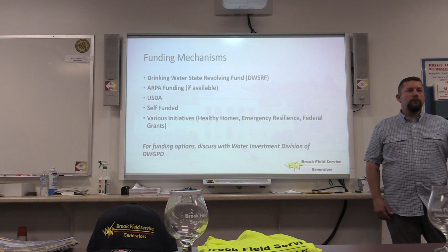Yeah, they have very good data. The one thing you have to remember with the data you're getting from them is that they're measuring in 15-minute increments. When a pump comes on, it's a lot faster than 15 minutes, so you're still not getting the reads of the inrush current for pumps that don't have VFDs. If you have VFDs on all your pumps, then yeah, it's really good data to use. But if you don't, you might want to have us take a look so that we can see the actual spikes. Generators can have a certain capacity to handle inrushes, but there's a voltage dip when that happens.